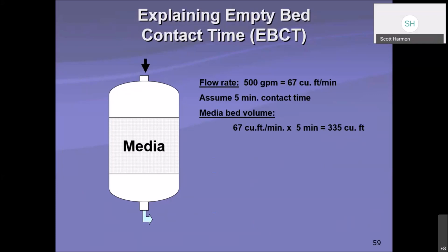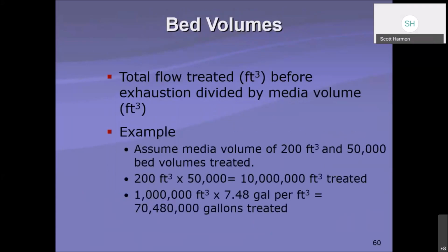So it's important to understand that these particular type of filters in this process are designed for certain flow rates, which we discussed earlier. So this actually gives you a visual representation of what that empty bed contact time is. And that is designed to make sure that the amount of flow going through your media, the water spends enough time in that media to have a chance to adsorb to the outside of any of the media grains.